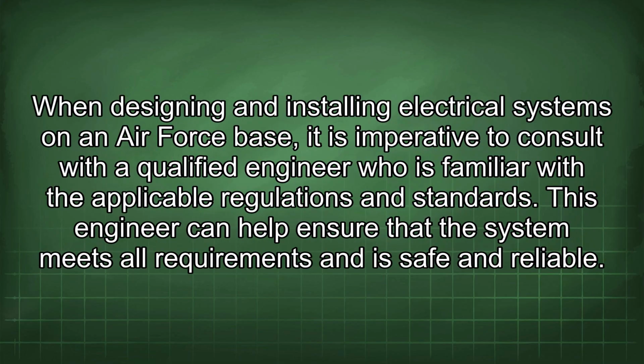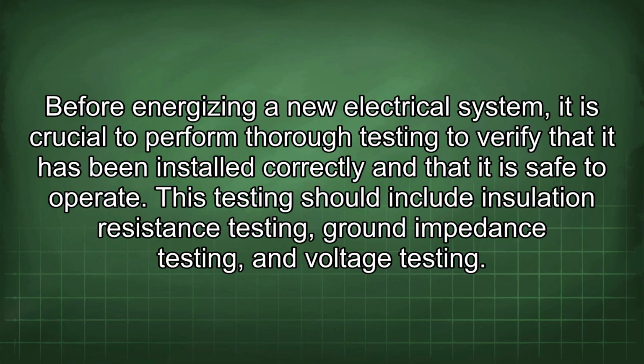When designing and installing electrical systems on an Air Force base, it is imperative to consult with a qualified engineer who is familiar with the applicable regulations and standards. This engineer can help ensure that the system meets all requirements and is safe and reliable. Before energizing a new electrical system, it is crucial to perform thorough testing to verify that it has been installed correctly and that it is safe to operate. This testing should include insulation resistance testing, ground impedance testing, and voltage testing.